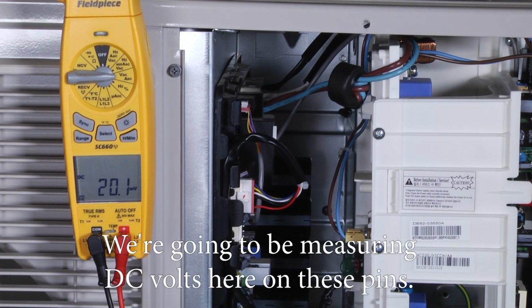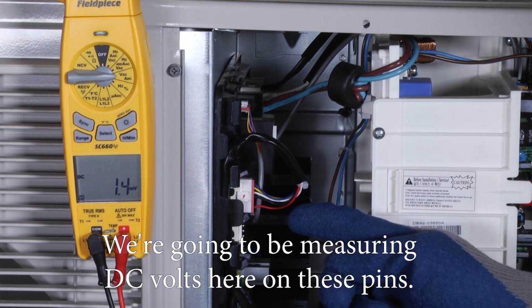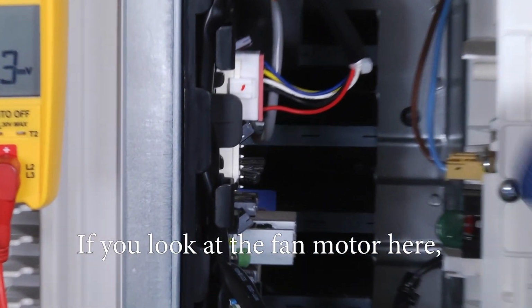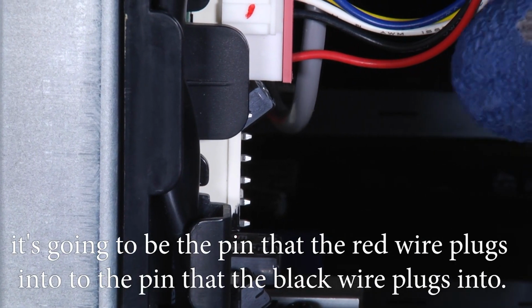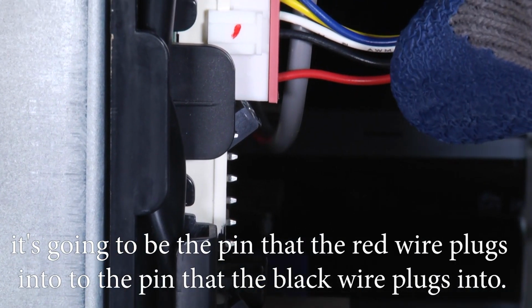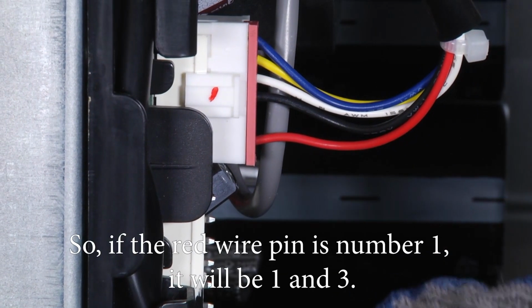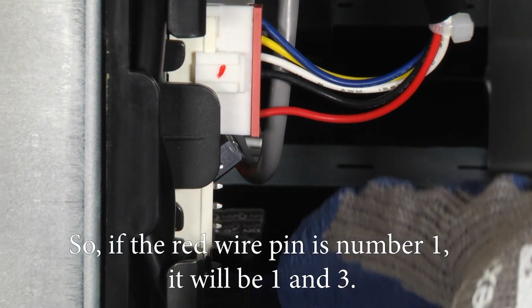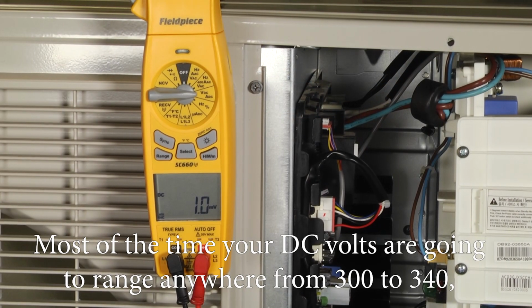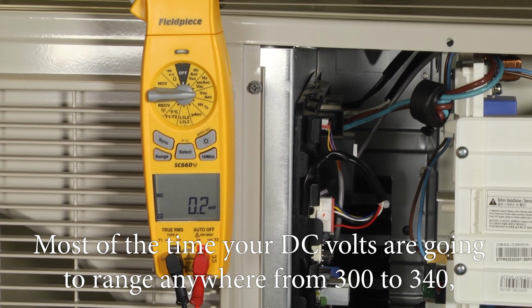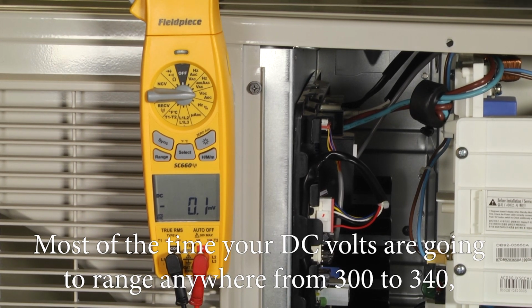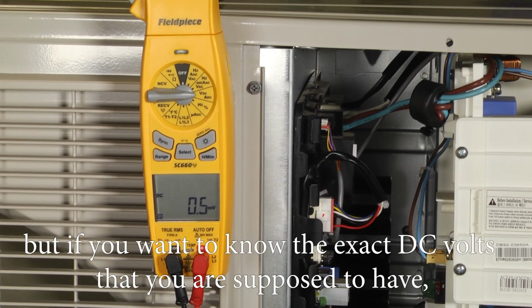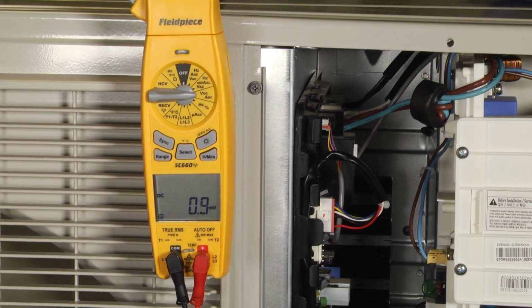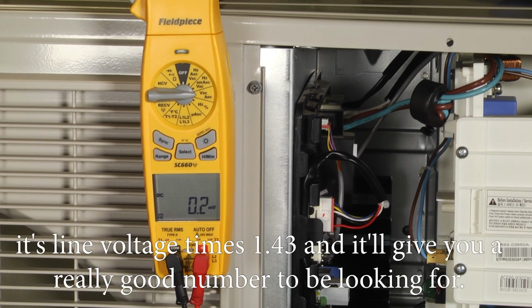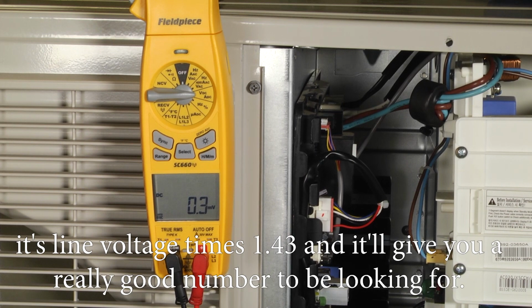All right, so we're going to be measuring DC volts here on these pins right here. If you look at the fan motor here, it's going to be the pin that the red wire plugs into to the pin that the black wire plugs into. So if red wire pin is number 1, it will be 1 and 3. Most of the time your DC volts are going to range anywhere from 300 to 340. But if you want to know the exact DC volts that you're supposed to have, it's line voltage times 1.43, and it'll give you a really good number to be looking for there.